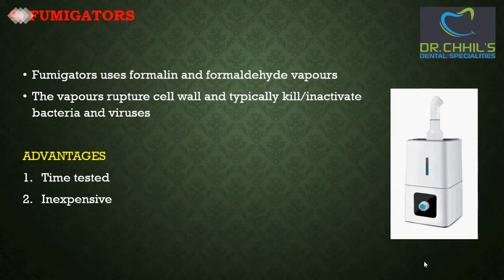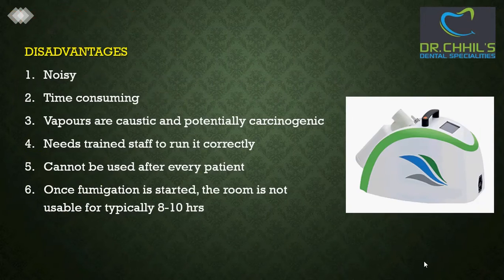Fumigators. Fumigators use formalin and formaldehyde vapors. The vapors rupture the cell wall and typically kill or inactivate bacteria and viruses. The advantages are that it is a time-tested procedure and it is inexpensive. Coming to the disadvantages, it is noisy, time-consuming, the vapors are caustic and potentially carcinogenic, it needs trained staff to run it correctly, and it cannot be used after every patient. Once fumigation is started, the room is not usable for a typical 8 to 10 hours.